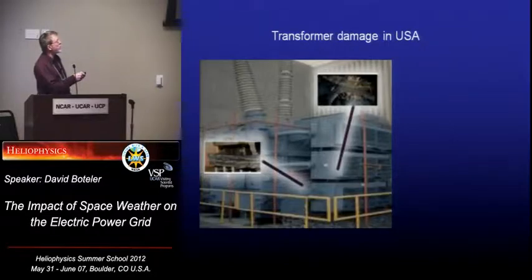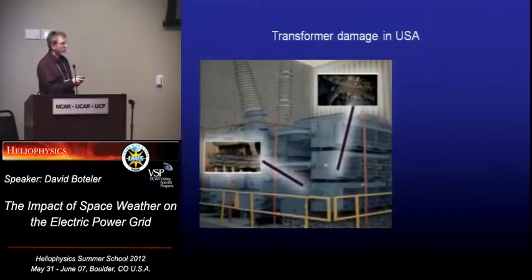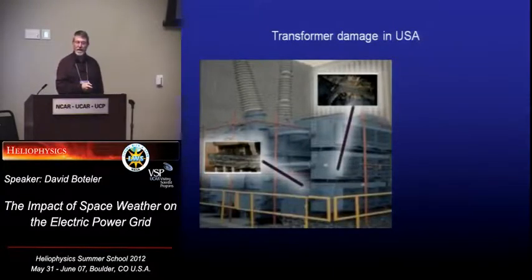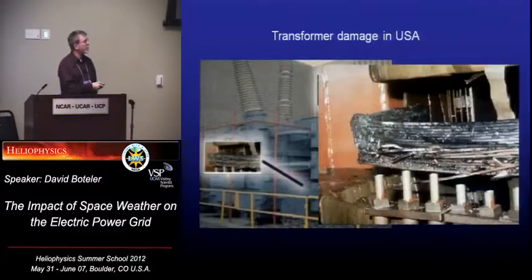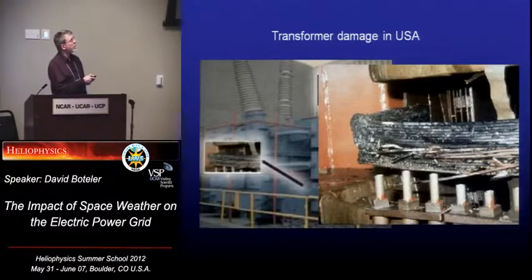But you can judge from the railings. These are normal waist height railings. So the person standing is about that high. So these are enormous constructions. They're about the size of a house, some of these big ones. So if you get that burnt out, then they're expensive and it's not easy to ship around and things like that. So anyway, they had problems with that. So they opened up the transformer, and that's what the windings look like inside. They'd overheated, and so that transformer had to be replaced.